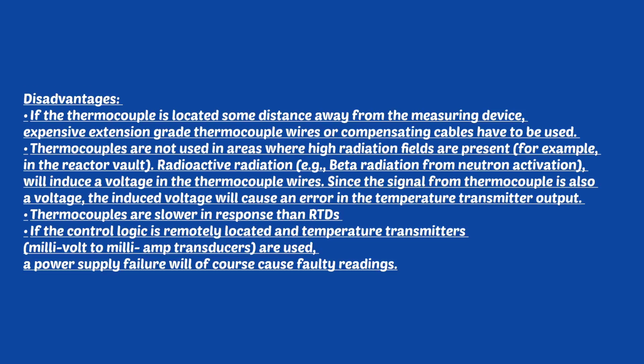Disadvantage 1. If the thermocouple is located some distance away from the measuring device, expensive extension grade thermocouple wires or compensating cable have to be used. 2. Thermocouples are not used in areas where high radiation fields are present.